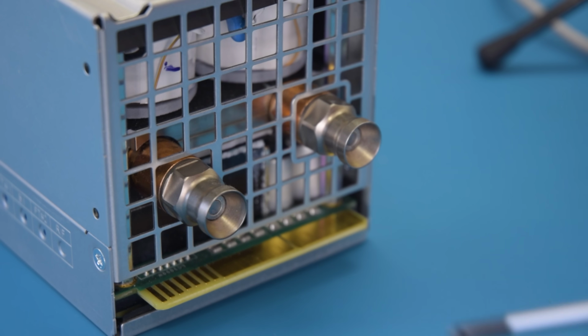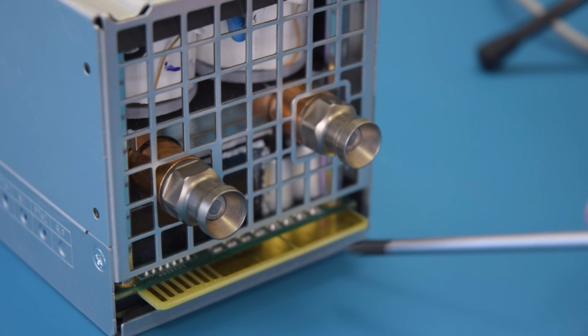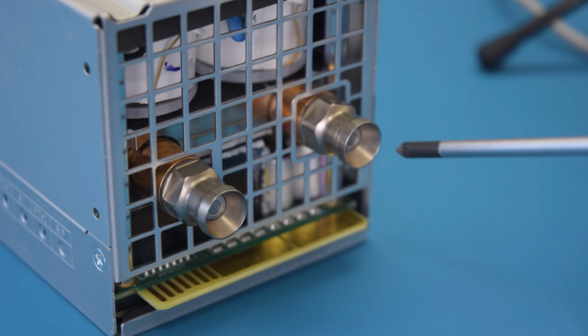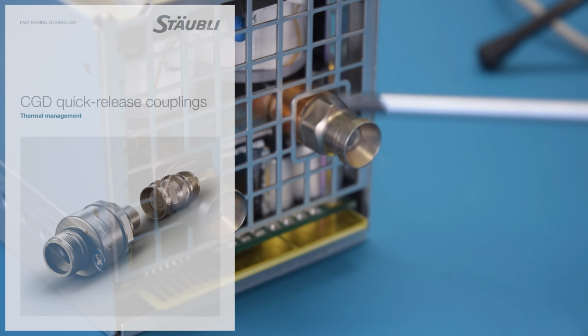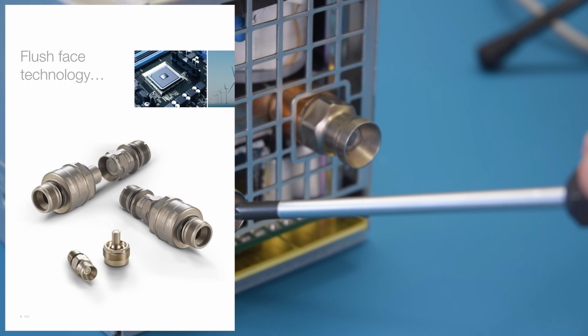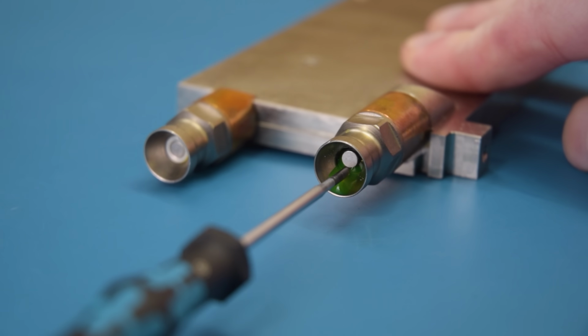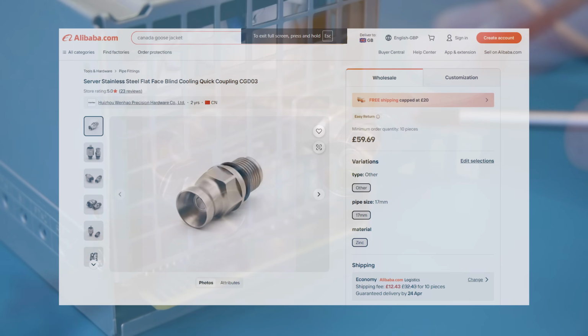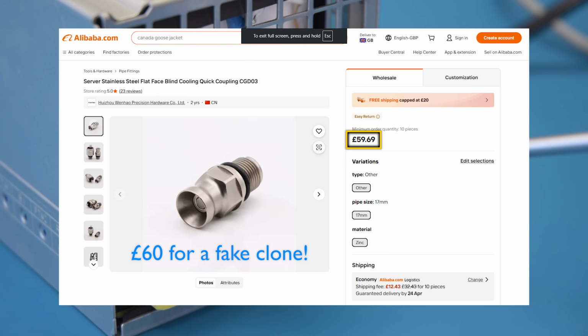These funky looking conical things just above the output terminals are dry break disconnects, a special type of fluid coupling that allows connections to be made or removed without having to drain the coolant, because they have automatic spring-loaded seals inside that prevent any coolant from leaking. These are normally quite pricey because of their mechanical complexity, and I'm hopeful that that's a sign of quality to come.